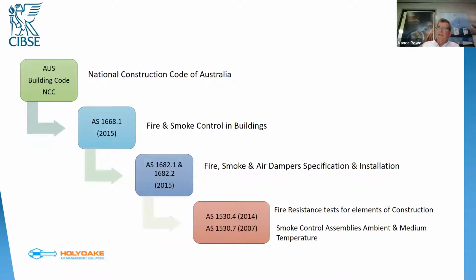Quick slide on how compliance works generally in our situation. Certainly using the deemed to satisfy route. We've got the Australian Building Code, the NCC, which refers to 1668.1, 2015, which then refers to 1682.1 and 1682.2, being the specification and installation of fire, smoke and air dampers. Those standards refer to AS 1530.4, 2014, for the fire resistant tests for elements of construction, and 1530.7 for smoke control assemblies. A little bit again on 1530.7.